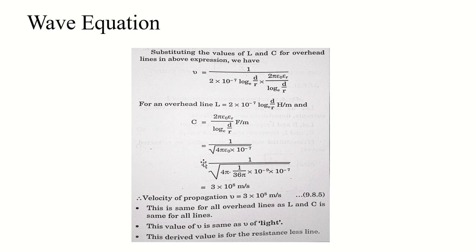In comparison with overhead lines, for cables the value of v is much less because of the relative permittivity. For air, εr = 1, so that factor cancels out. For soil, εr is greater than 1, making v even smaller. For underground cables, the dielectric constant εr varies between 2.5 to 4, so v varies accordingly as εr varies.